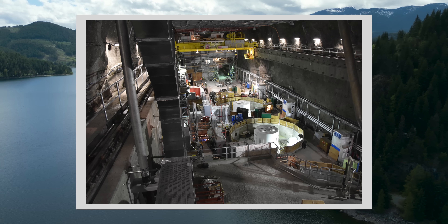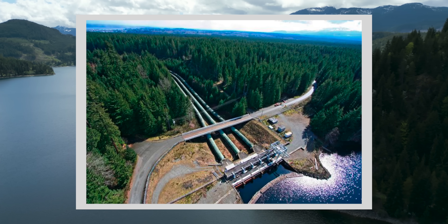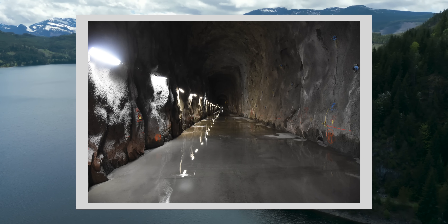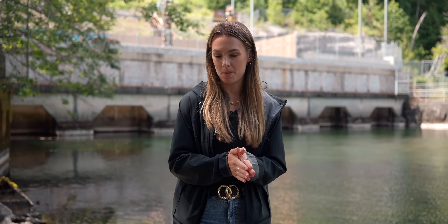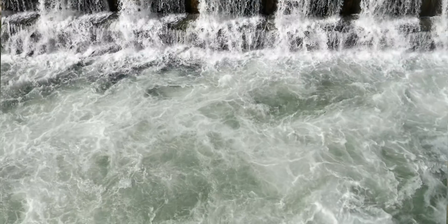In order to make upgrades so that this dam can be much more resilient to seismic activity, a number of other things had to happen first. The powerhouse, which used to be above ground, had to go underground and now sits in a 10-storey-high underground cavern the length of an NFL football pitch. Additionally, the penstocks where water flows also had to be moved underground. Now that project has been completed, they can kick-start the next phase of work — lasting six years — to make this less vulnerable to seismic activity, ensuring water could pass safely downstream should there ever be a magnitude 9 earthquake.